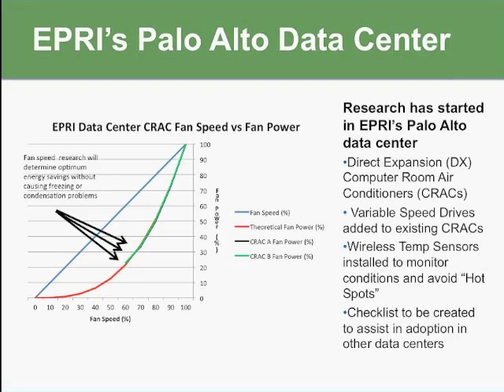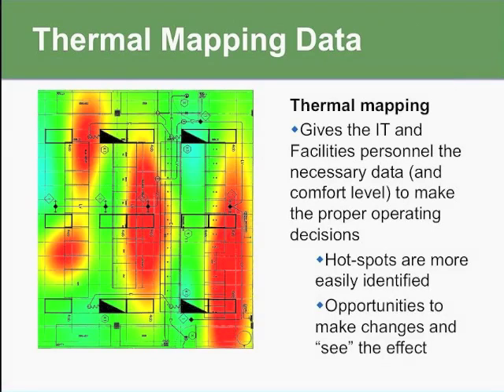And what's great is that we've got all these wireless temperature sensors installed now. We can monitor exactly what's going on throughout the data center, checking to make sure that everything is okay, no hot spots are being created, and so far everything is going per plan. As I said, the original setup of the data center racks, they did a pretty good job of keeping the hot aisle cold aisle arrangement.